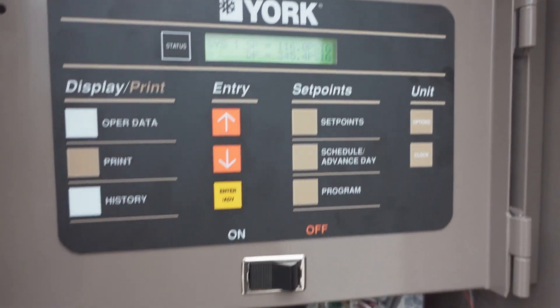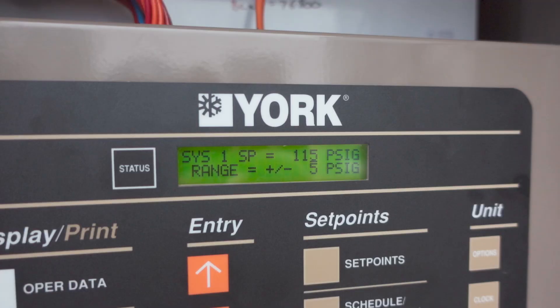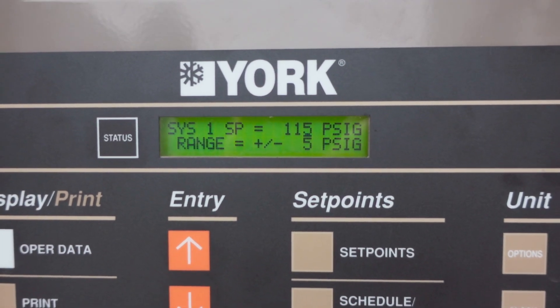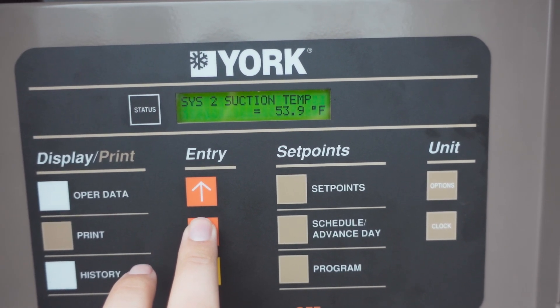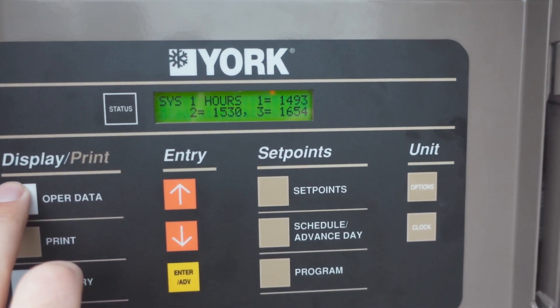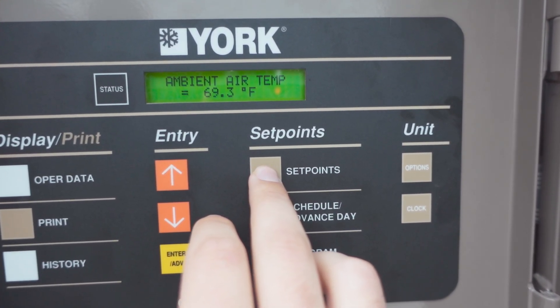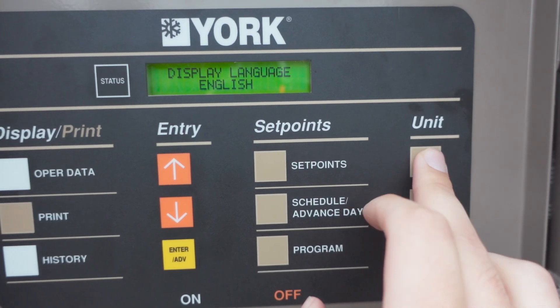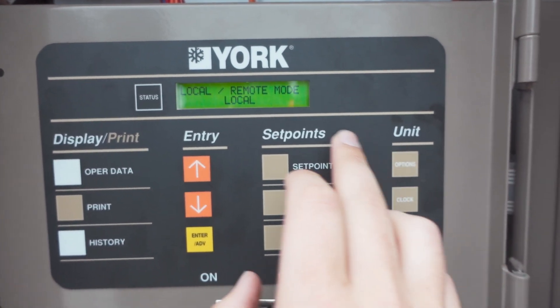There's another concept where we use suction pressure to stage compressors, and that used to be a lot more common. It was done through suction unloaders on old recip-style compressors — they had little unloader valves you don't really deal with much anymore. This technology still exists, and I had a job recently where it ended up being the better option because of the design parameters on site.